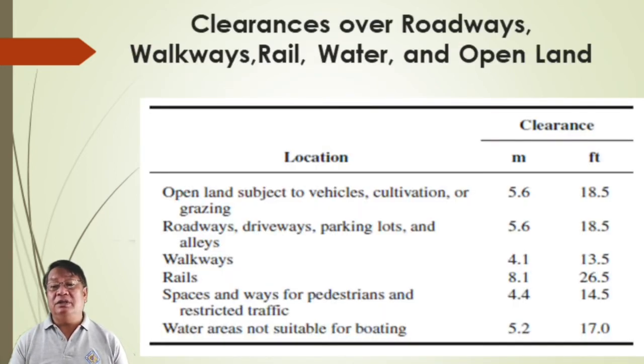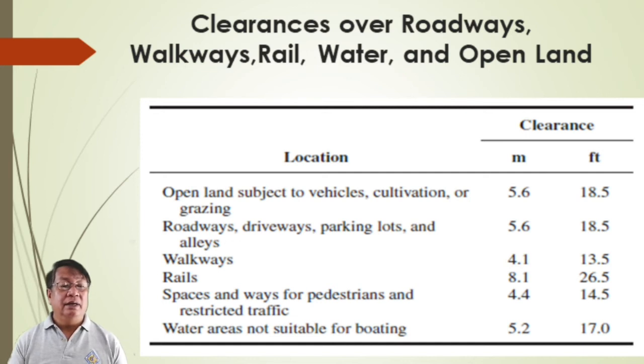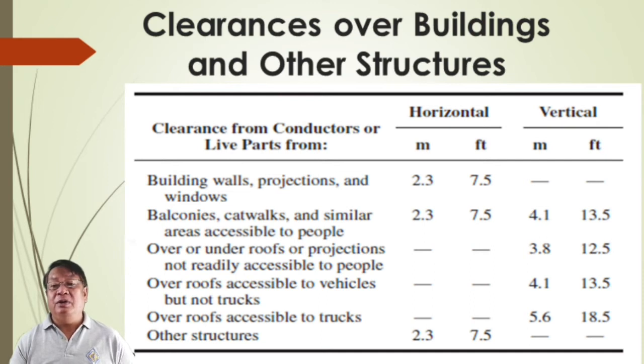Clearance over roadways, walkways, rail, water, and open land: for railways, not less than 8.1 meters; space for pedestrians with restricted traffic — 4.4 meters; water areas not suitable for boating — 5.2 meters. Clearances over buildings and other structures include horizontal clearances for building walls, projections, and windows, and vertical clearances as well.